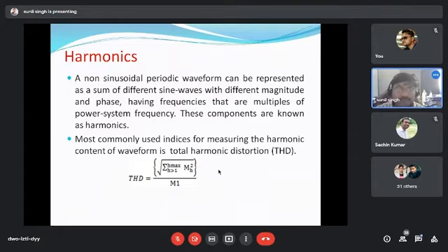So harmonics. What is the harmonics? These multiple decomposed waveforms are known as the harmonics. The first harmonic is the fundamental harmonic, 50 hertz frequency. The second harmonic, 100 hertz frequency. The third harmonic, 150 hertz frequency, having a different magnitude, but lesser than the fundamental, and a different phase. So these components are called the harmonics.